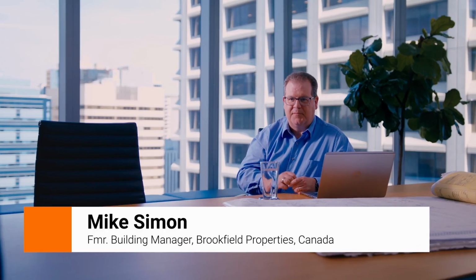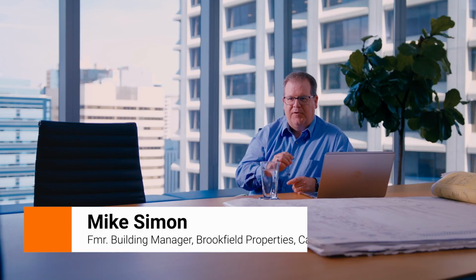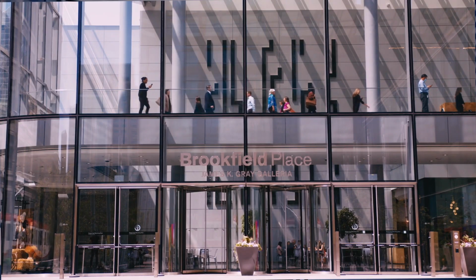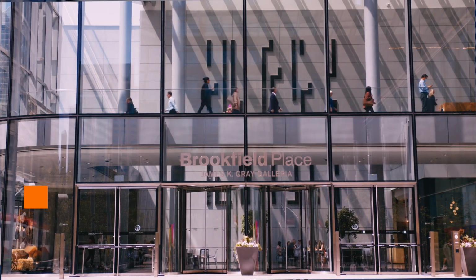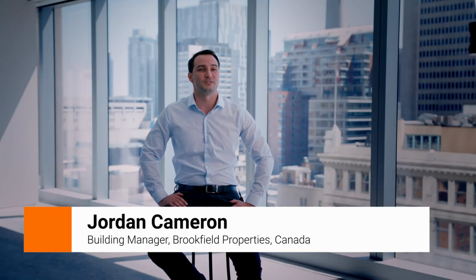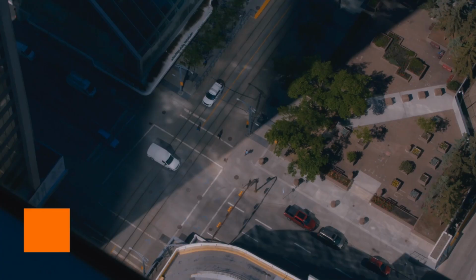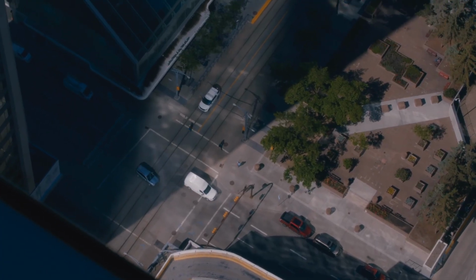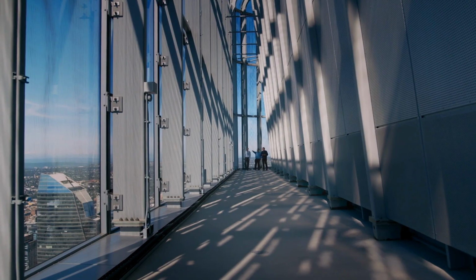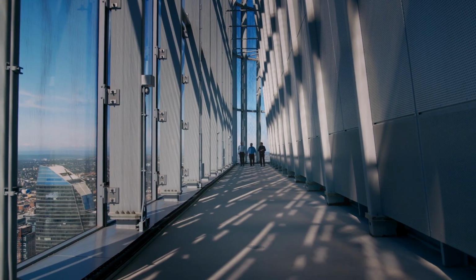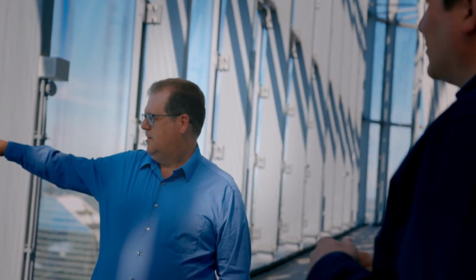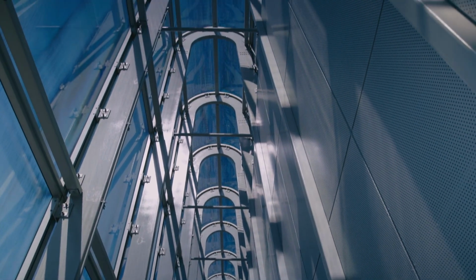It's kind of unheard of to be able to do that without having the tenants be aware of the changes happening within their space. I was shocked on the energy savings that we were able to maintain. We saved 8.9 million liters of water flow per day in the primary heating system alone. Even though the building was built to the highest technology standards, there was still room for improvement.